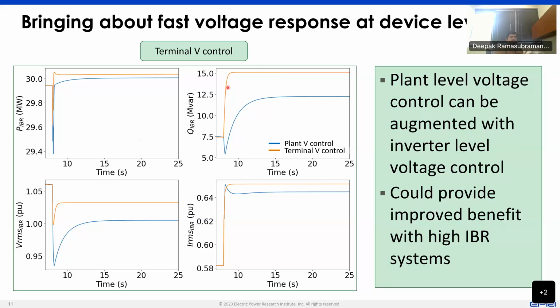We have done some preliminary studies looking at how, if the distribution network with all of these inverters has to rely on the transmission network, how much capacity is needed on the transmission network to provide that service to the distribution network, as opposed to if that service was provided in the distribution network itself. The capacity could sometimes be a drastically different number when it's provided within the distribution network itself. Mm-hmm. Thank you.